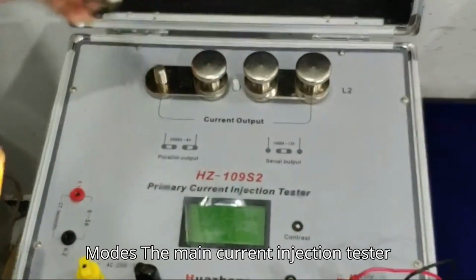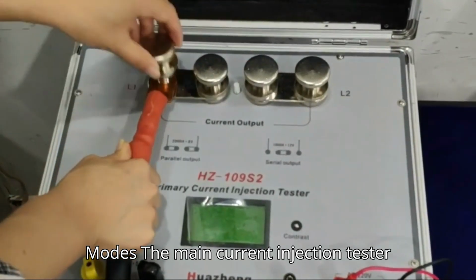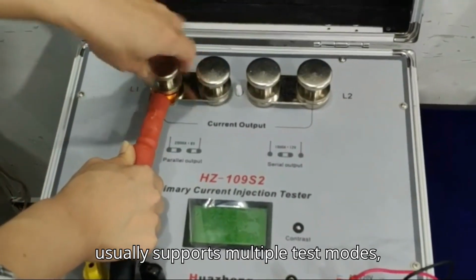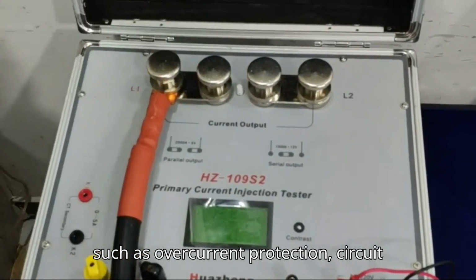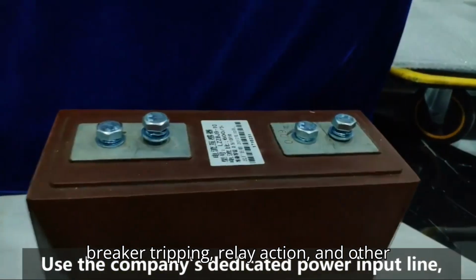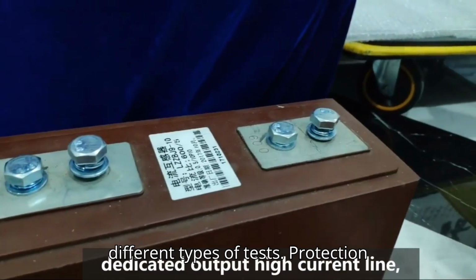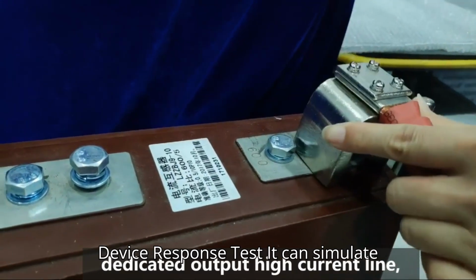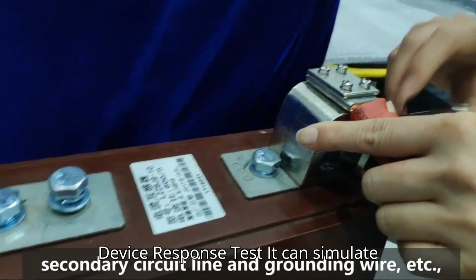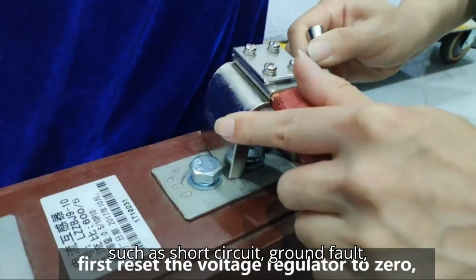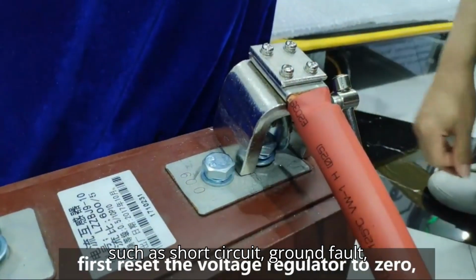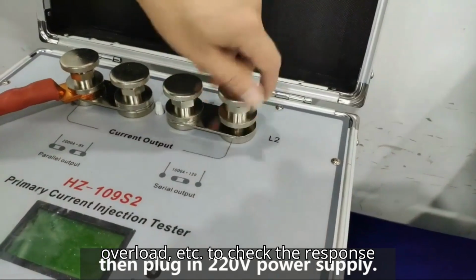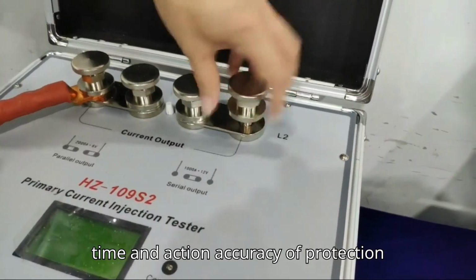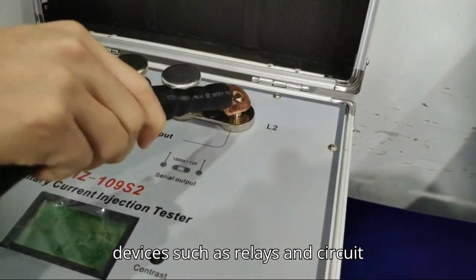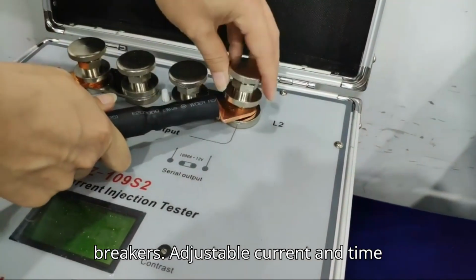Multiple test modes. The main current injection tester usually supports multiple test modes, such as overcurrent protection, circuit breaker tripping, relay action, and other different types of tests. Protection device response test. It can simulate different types of electrical faults, such as short circuit, ground fault, overload, etc., to check the response time and action accuracy of protection devices, such as relays and circuit breakers.